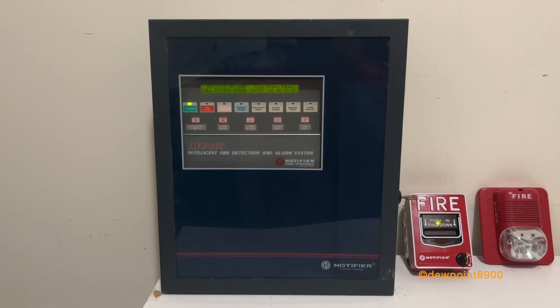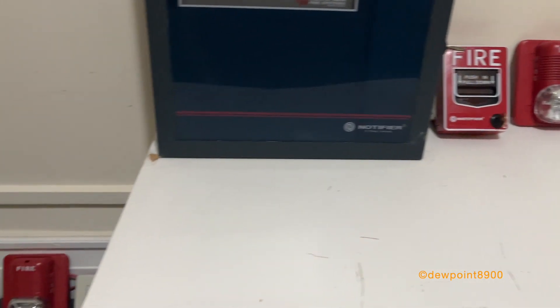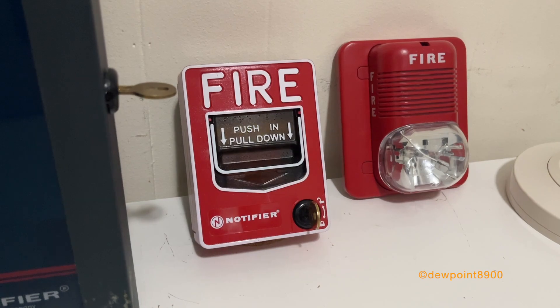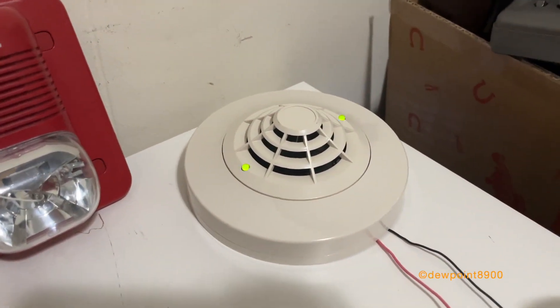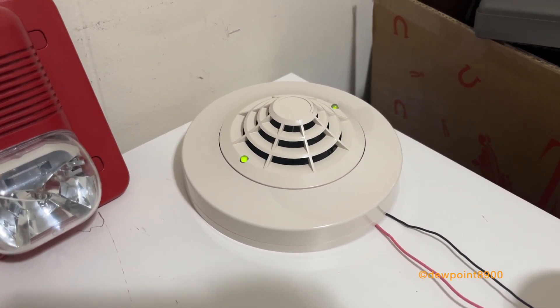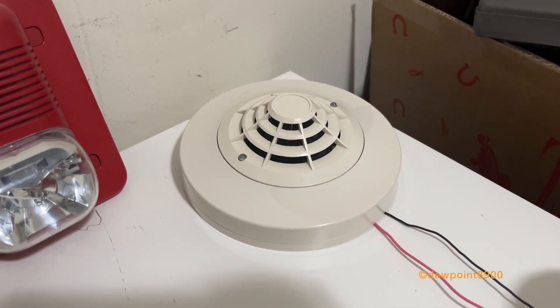For this demonstration, all initiating devices are compatible with FlashScan protocol, but can also run on CLIP in retrofit applications. Right here is an NBG-12LX pull station. This is an FST751 heat detector on a B224RB relay base. In a real system, this relay base could be connected to a door holder or some equipment, which can be shut off when this detector alarms.